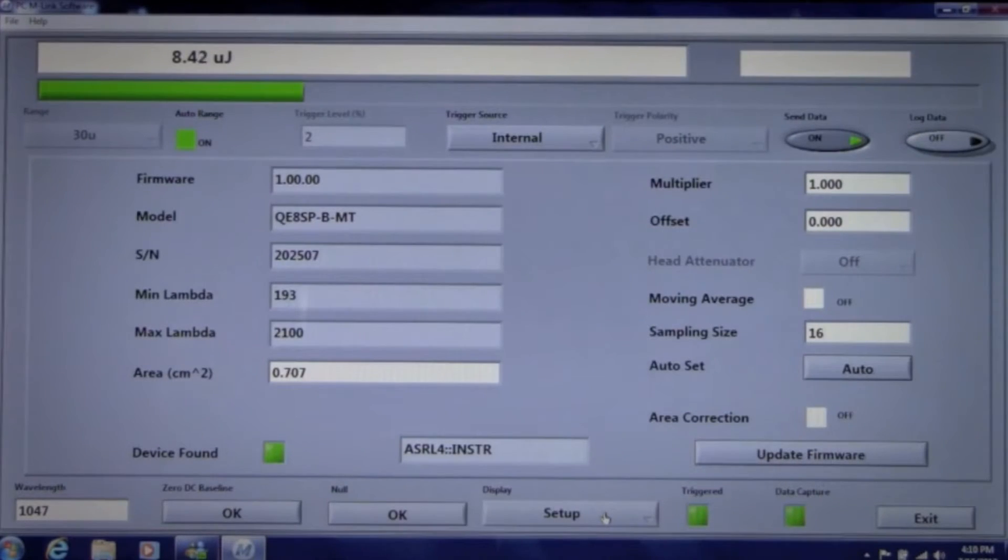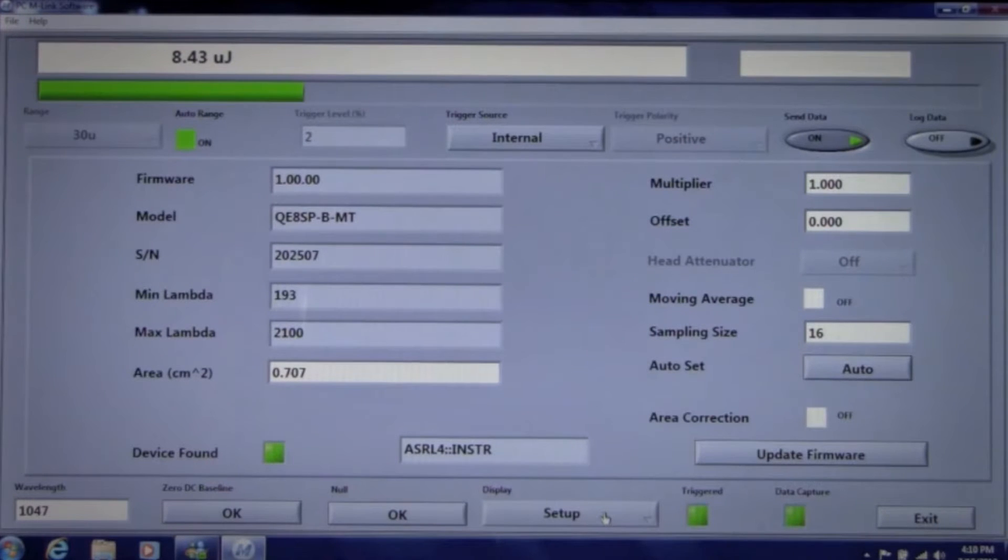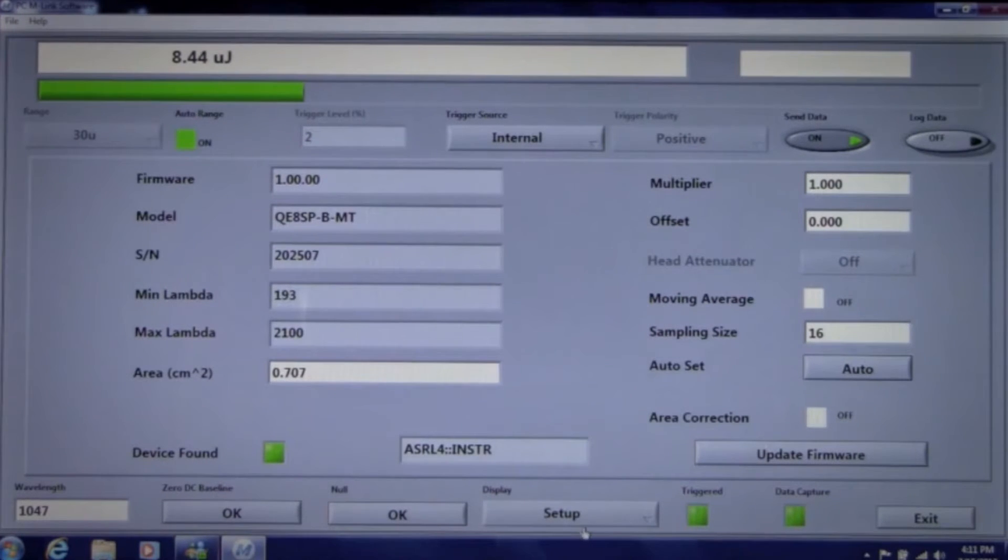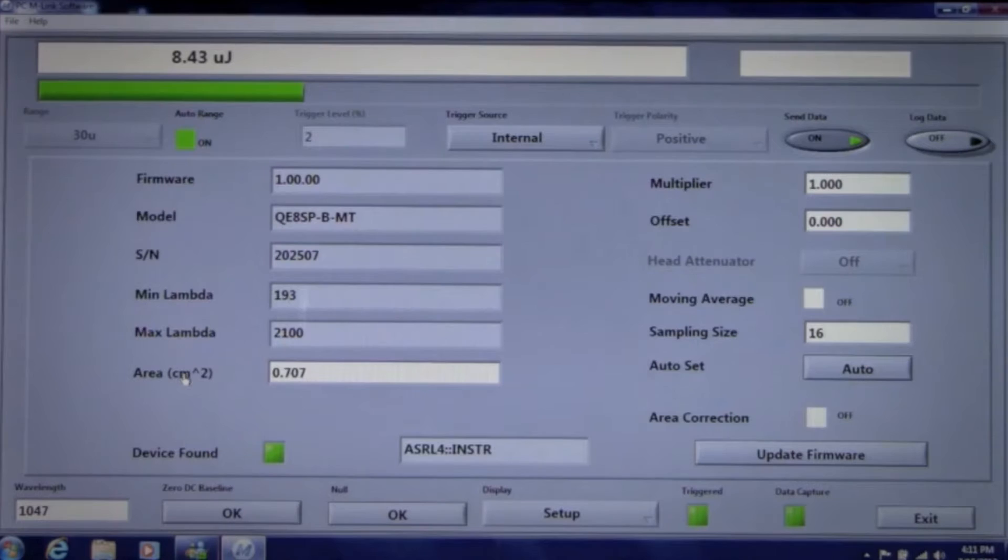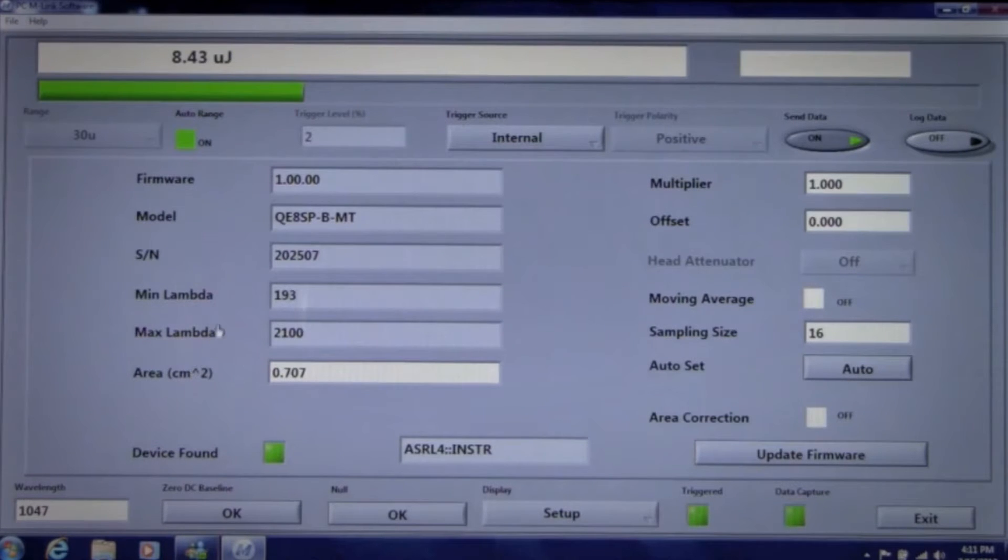When you bring up the M-Link software, the first thing you'll see is the setup screen, where you'll be able to read the probe model and serial number, wavelength range, and area, information that is stored in the probe EEPROM.